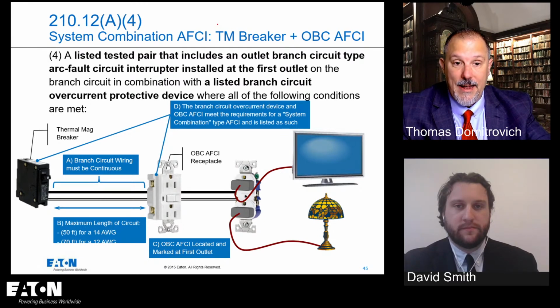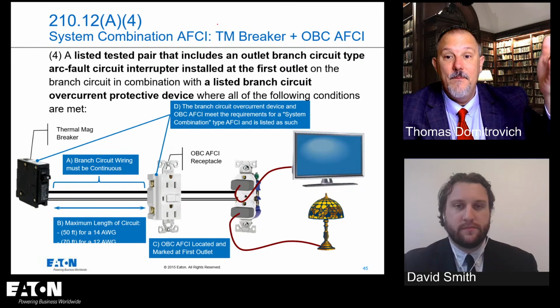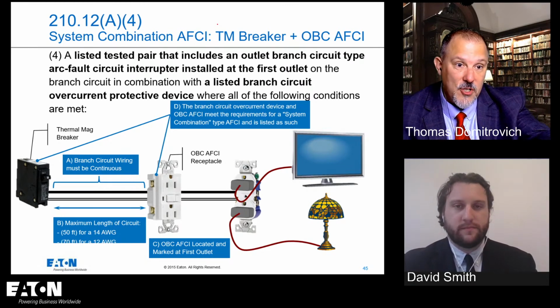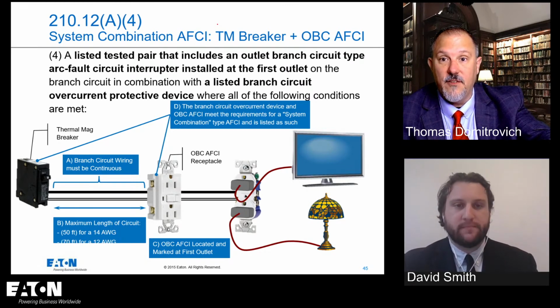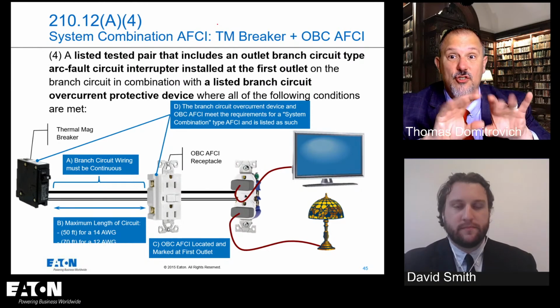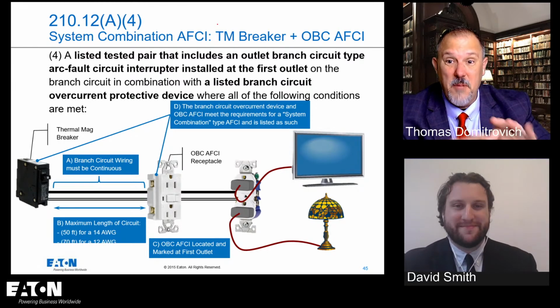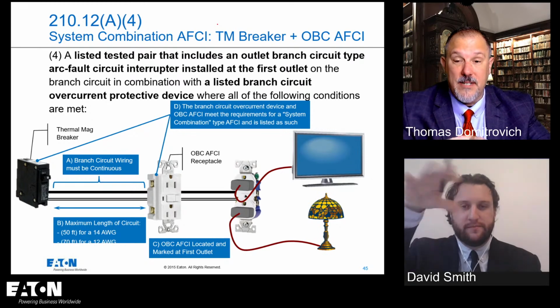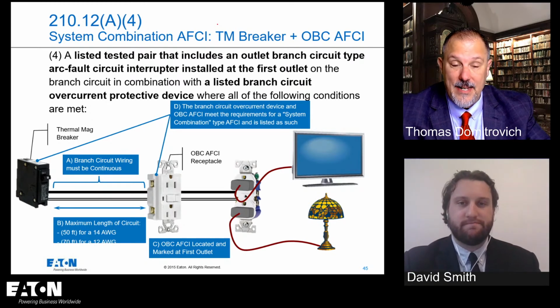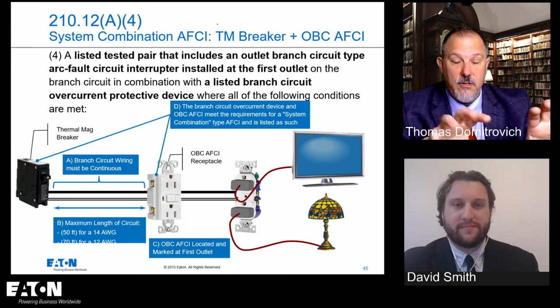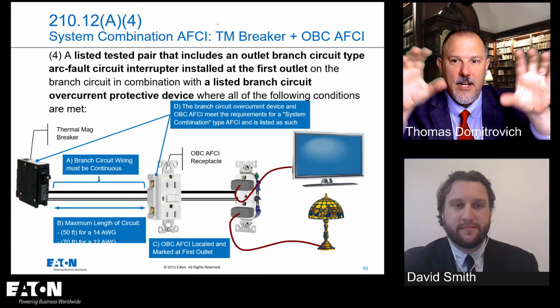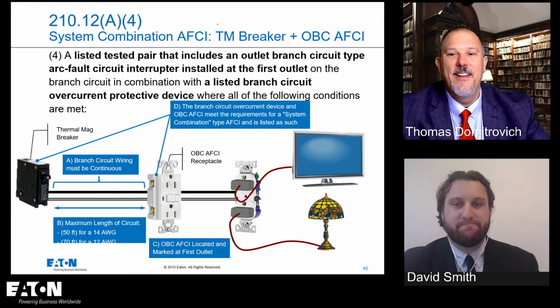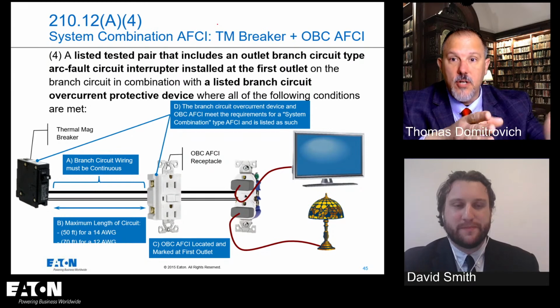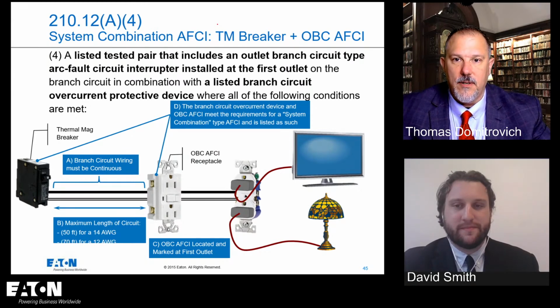And you can buy a listed device upstream, which is basically a UL 489 device. Now we have to put a little bit more extra sauce in the mixture to be able to provide that protection and pass the tests. But we have those two devices that are available, identical. And we provide the protection of the home run circuit and everything downstream.